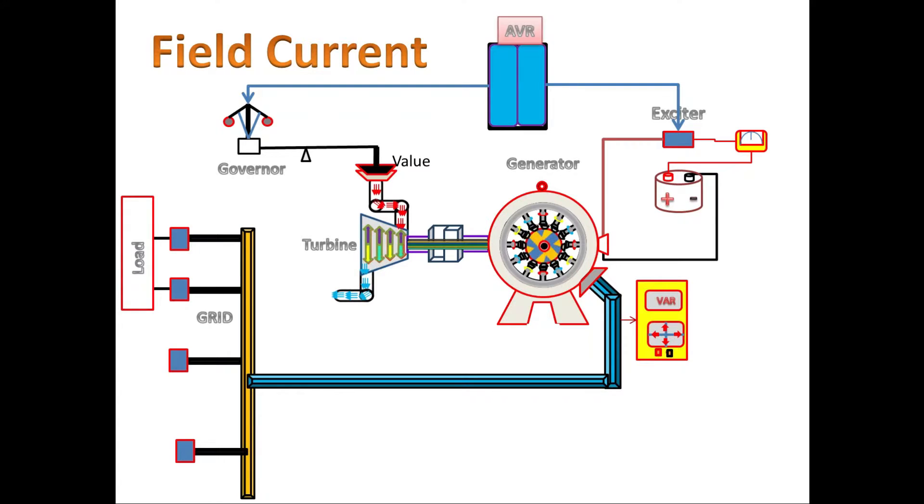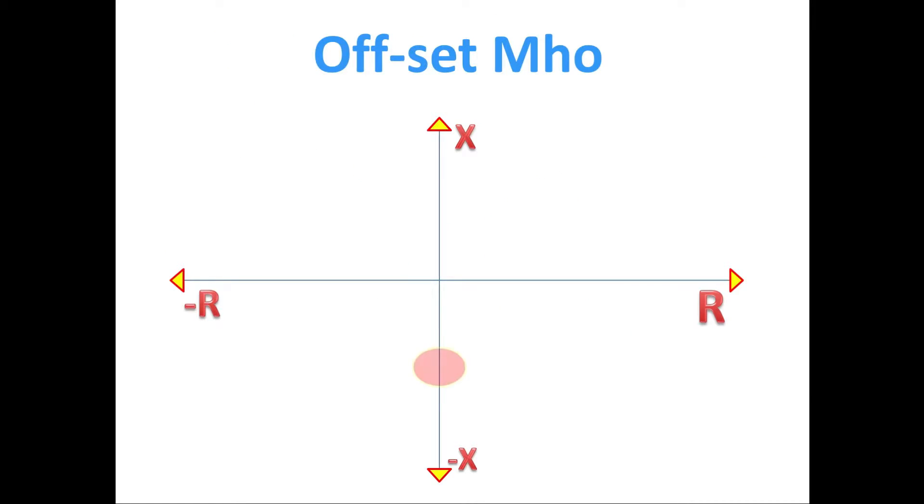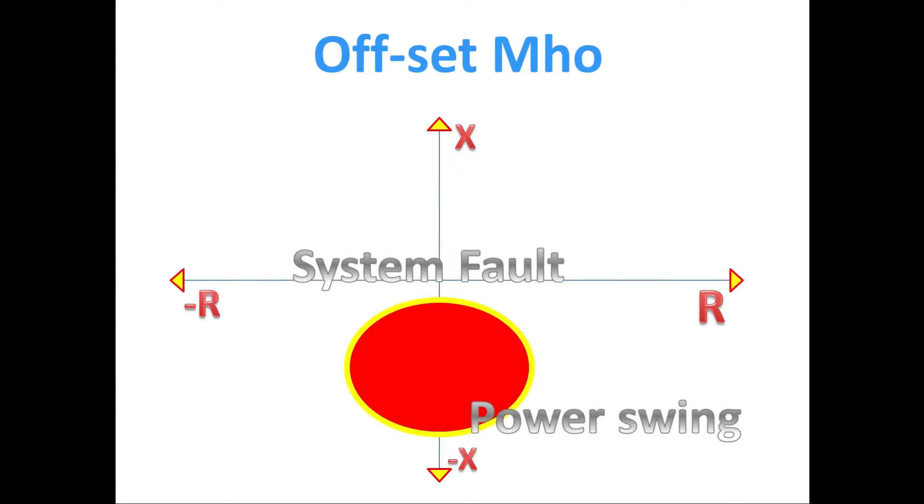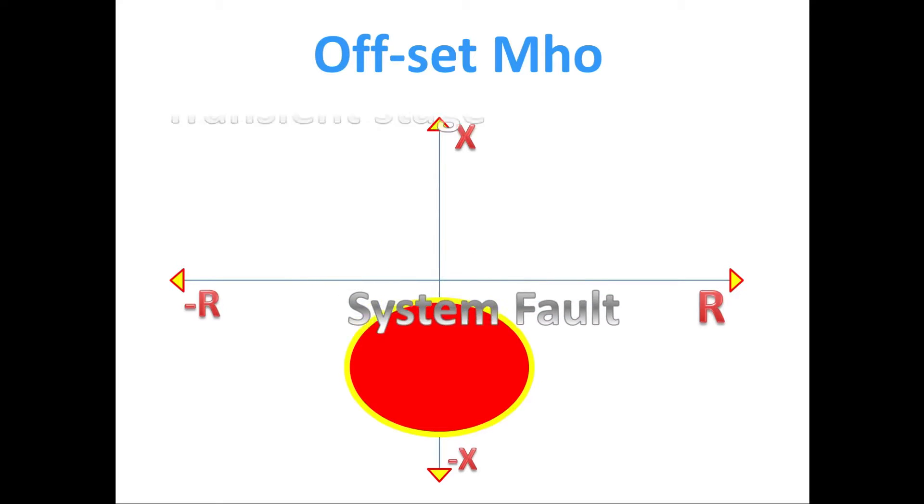The third one is by using impedance method. In that, we have a special one, offset Mho. This is one of the successful methods to detect the loss of field. And also it avoids more mal-operations such as for power swing fault, system faults such as heavy short circuit and earth fault, and also stable transient condition. In this offset Mho, we will see a little deeper.